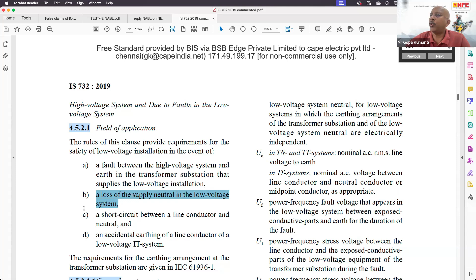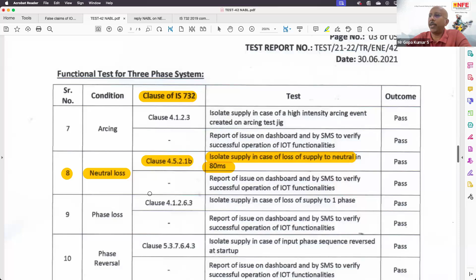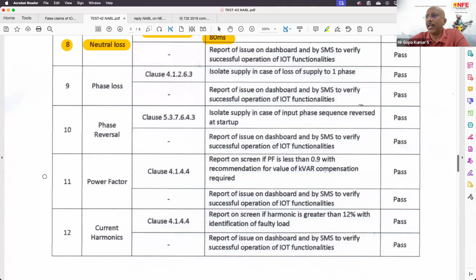Now, if you look at the test report as a whole, they are visually inspecting. I don't know how they visually inspected that the disconnection happened in 80 milliseconds. So like this, various of these tests which are made in the laboratory have absolutely no relation with the actual content of the standard. They are just referring to something to make the users fooled.